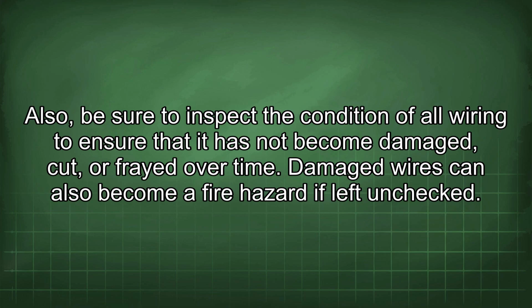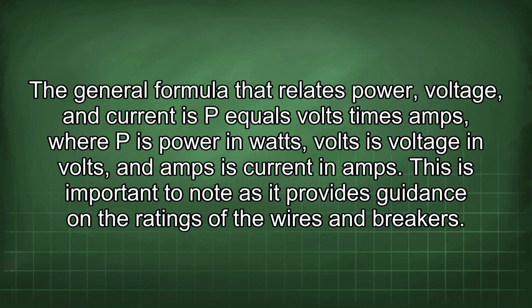Also, be sure to inspect the condition of all wiring to ensure that it has not become damaged, cut, or frayed over time. Damaged wires can also become a fire hazard if left unchecked. The general formula that relates power, voltage, and current is P equals volts times amps, where P is power in watts, volts is voltage in volts, and amps is current in amps. This is important to note as it provides guidance on the ratings of the wires and breakers.